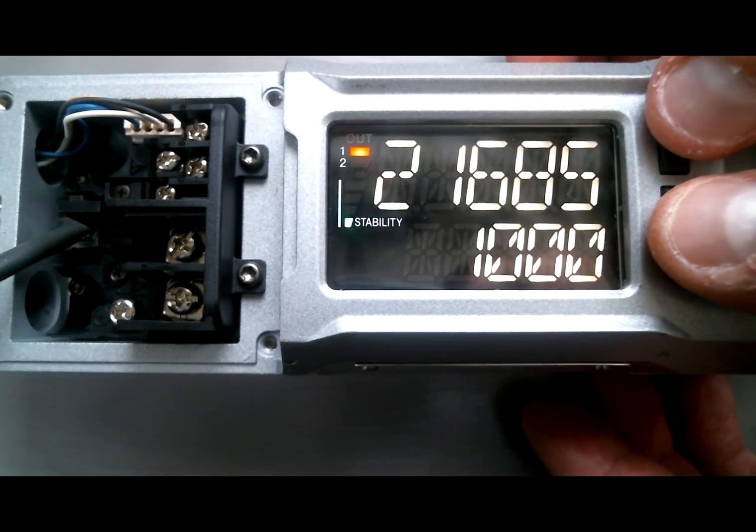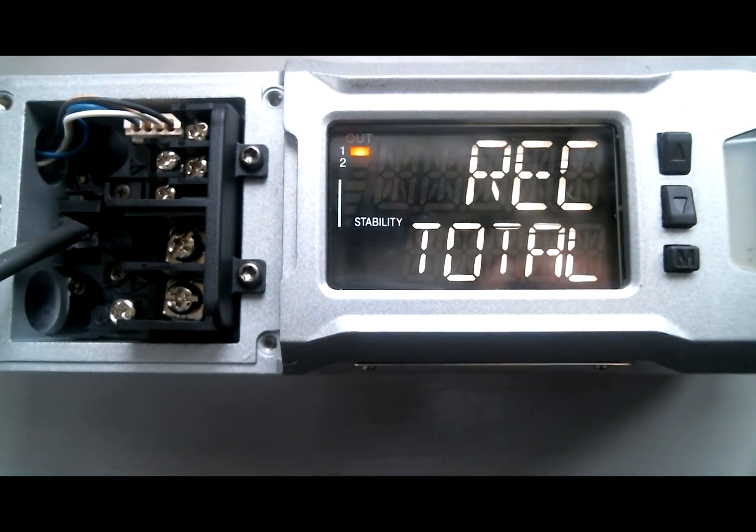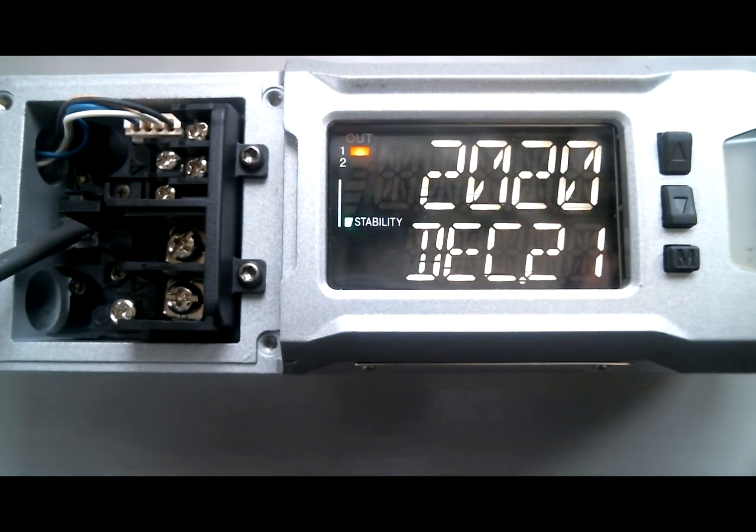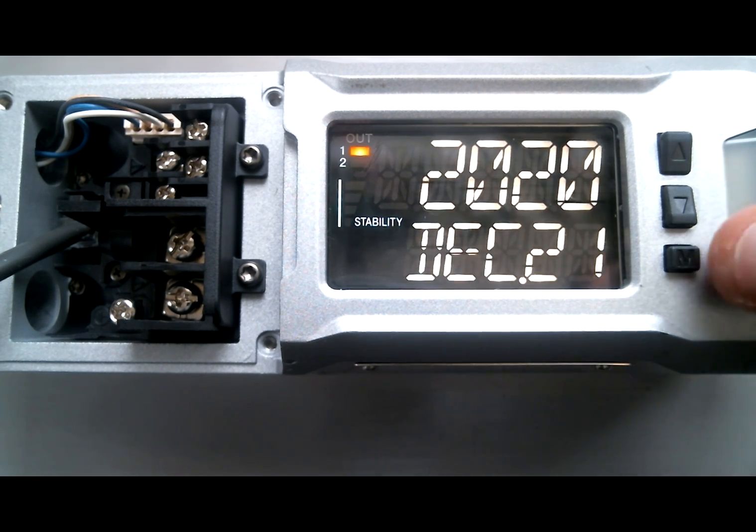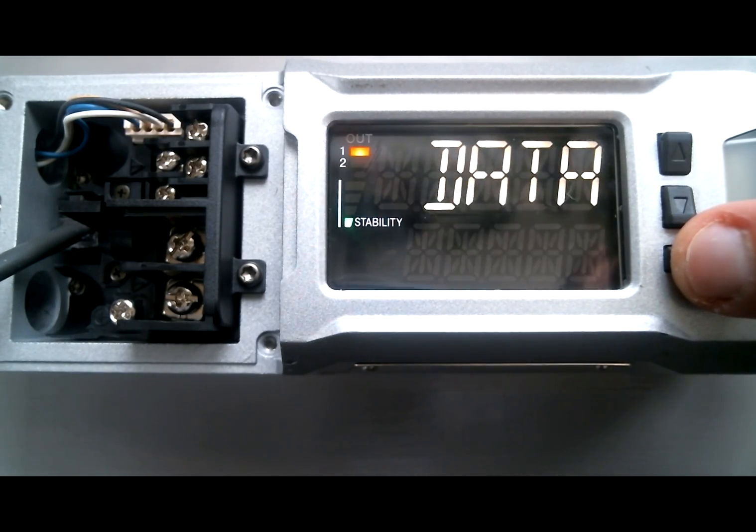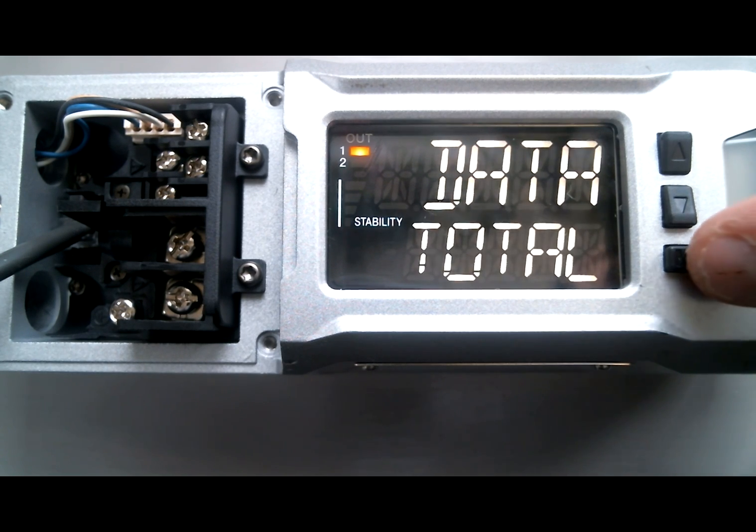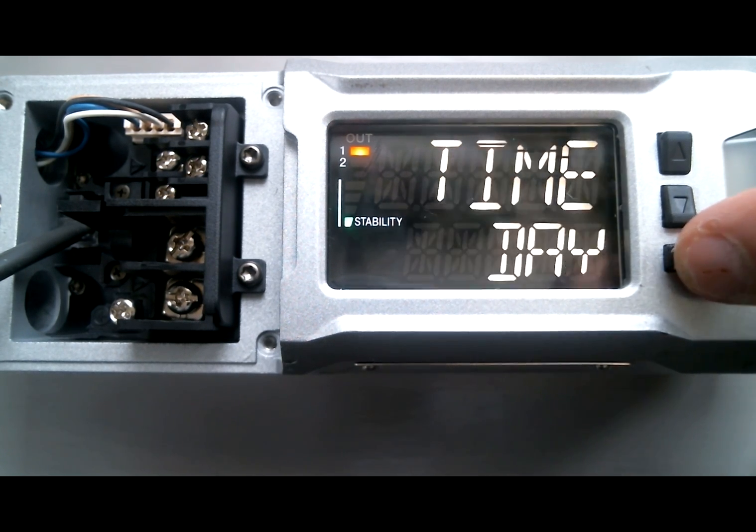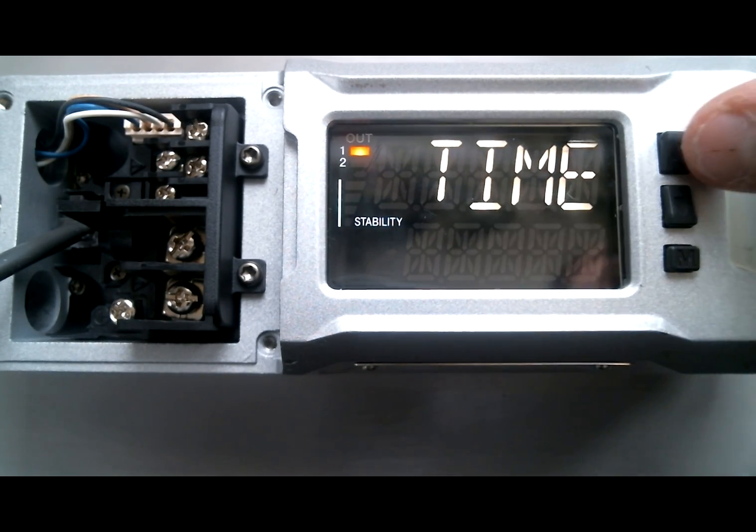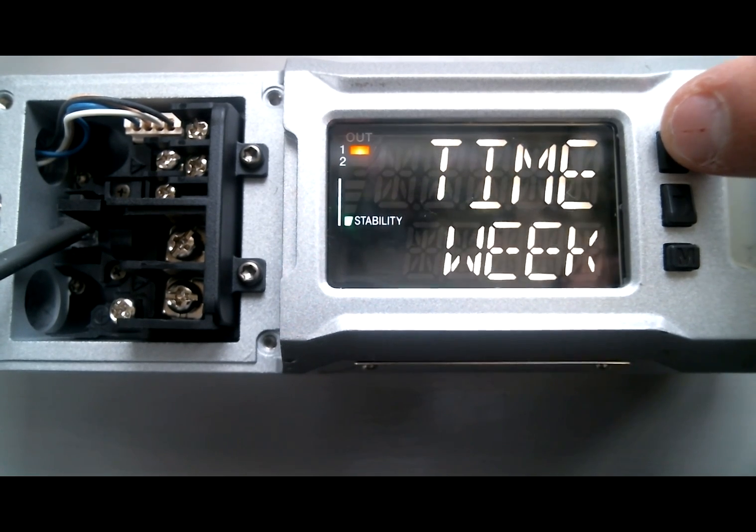To open the full-time recording display, hold Mode, Down, and Up together for three to five seconds. This will prompt for the date you want to view. Hold Mode to select the data type, in this case Total. Tap Mode to select the interval.